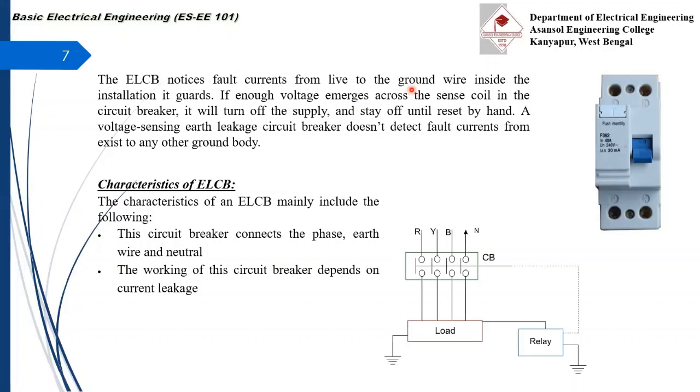Now you can see that in this ELCB device, the minimum current rating is 30 milliampere. And the voltage rating you can see is 240 volt AC, because the AC notation is given here, right? And current is 40 ampere and it is F-type device.